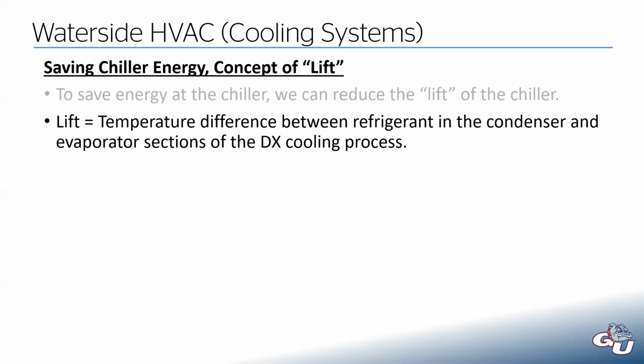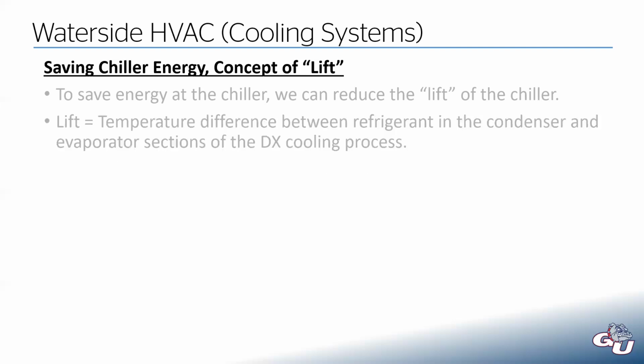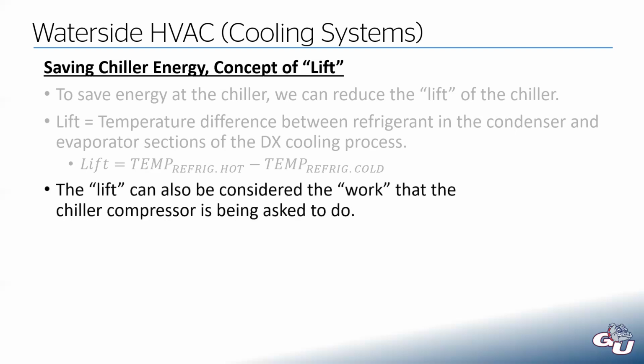And the high line running horizontal, that's our condenser temperature, and the low line running horizontal is our evaporator temperature. So the lift is just the temperature difference between the hot side and the cold side of our refrigerant process. And that lift is ultimately the work that the compressor is doing. Because remember, the compressor is the device that makes this whole thing work with the refrigerant, and the lift is that compressor work. If you have a very high delta T, which would be a very high lift, that means your compressor is doing a lot of work.